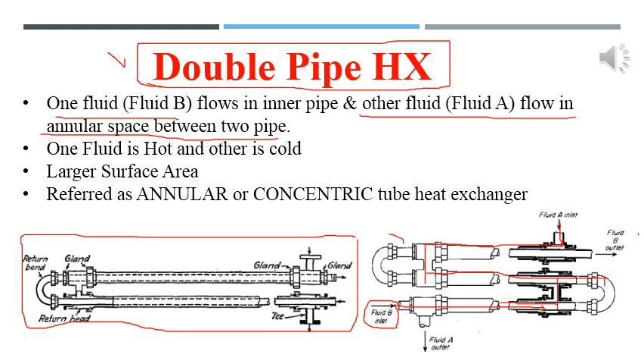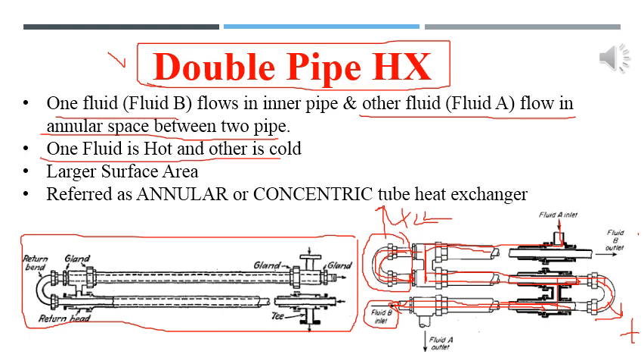The hot fluid passes through one section and then the next, with heat transfer occurring along each leg. It is our choice whether to introduce the hotter fluid in the annular side or the inner pipe. In parallel flow configuration, the heat transfer will be less, while in counter-current flow the heat transfer will be more, since the temperature difference remains constant from inlet to outlet. The double pipe heat exchanger is also called the annular or concentric tube heat exchanger. It is used in industry for applications where only a small amount of heat transfer is needed.